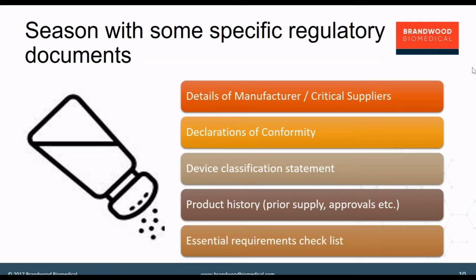A classification statement. So again, as we discussed before, the regulatory plan and requirements should normally be adequately defined upfront of the product development, and so those classification pathways should be determined as early as possible. This is at the end of the process confirmed once there is full definition of the product and all specifications have been produced and all verification details have been implemented. So classification statement, regulatory classification statement in the relevant jurisdiction.